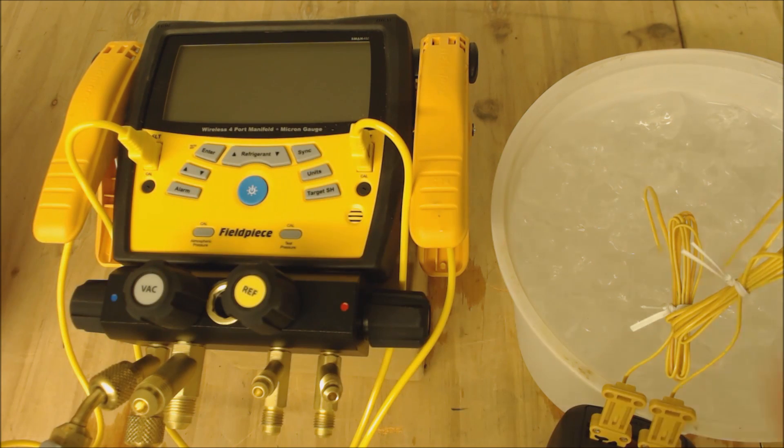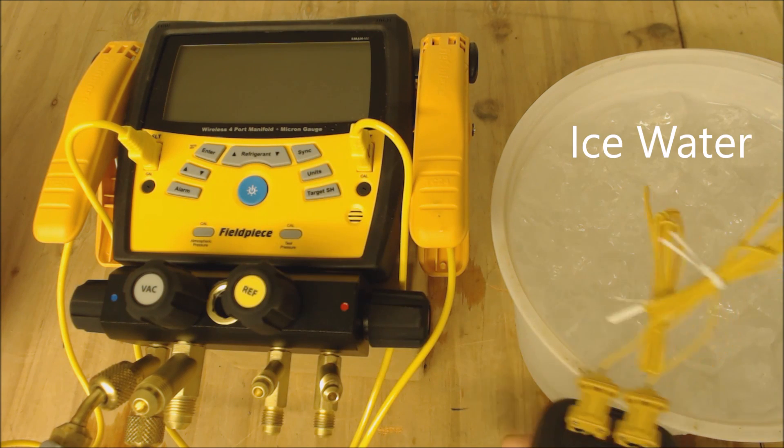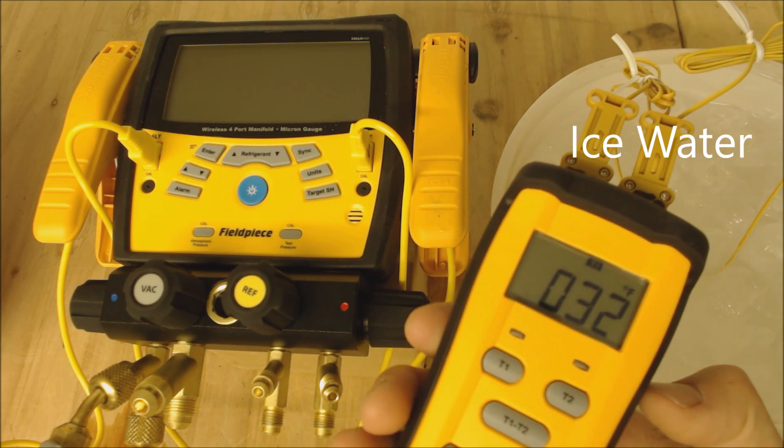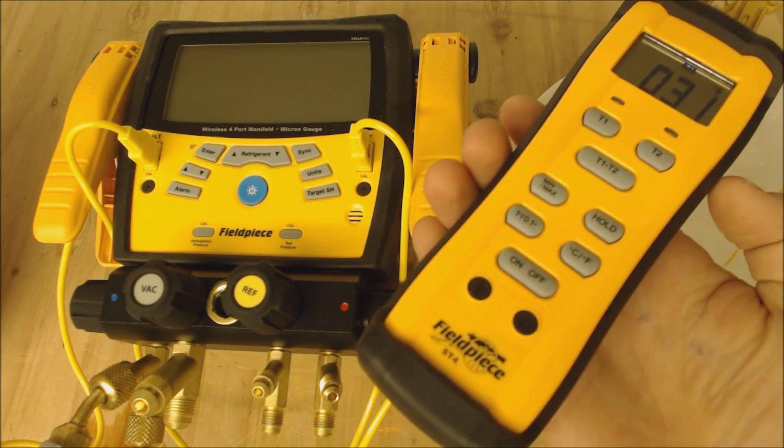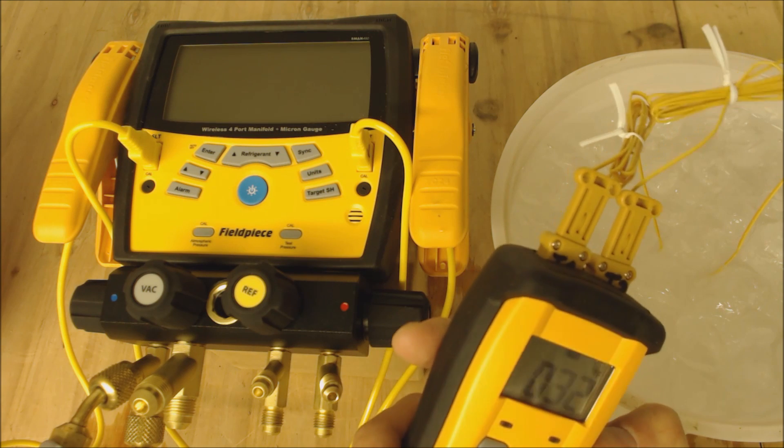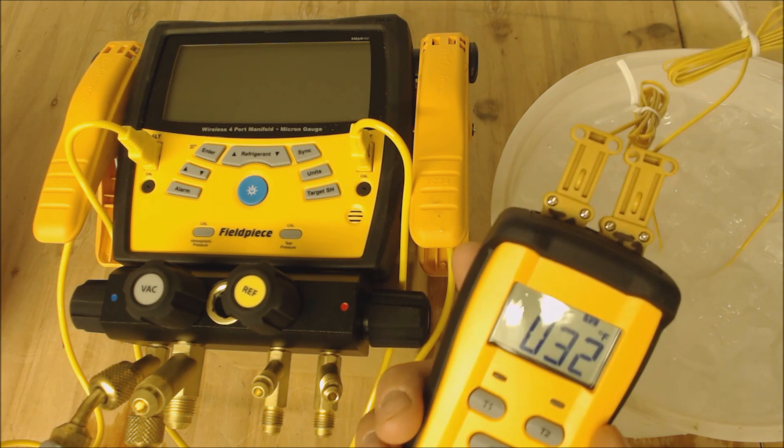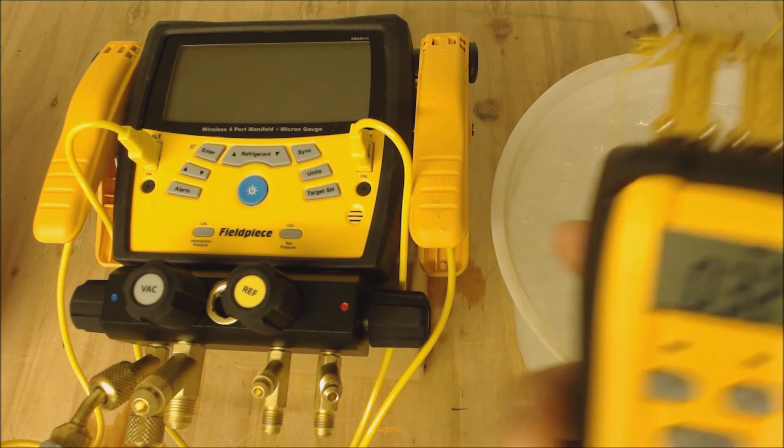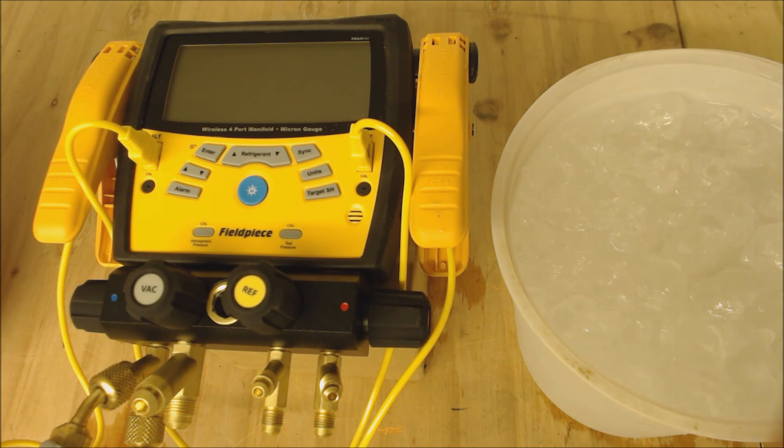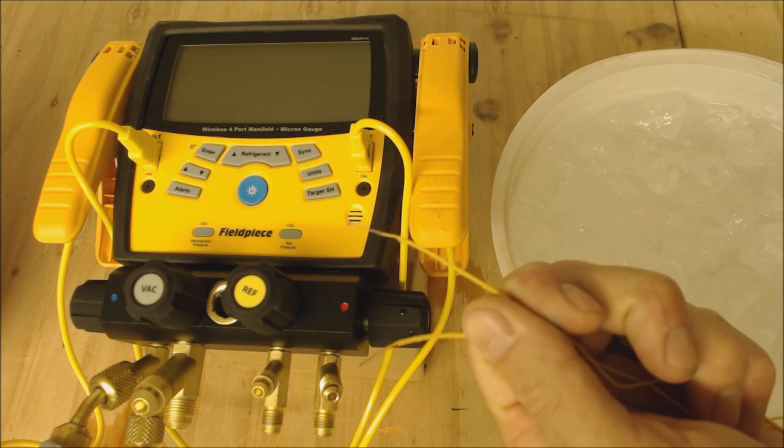The first thing we're going to start with is temperature. We have each of these clamps, a bucket of ice at 32 degrees, and here I have a Fieldpiece ST4. You see that it's 32 degrees on T1, and switching to T2 it says 32 degrees. That's with these small bead type temp sensors.